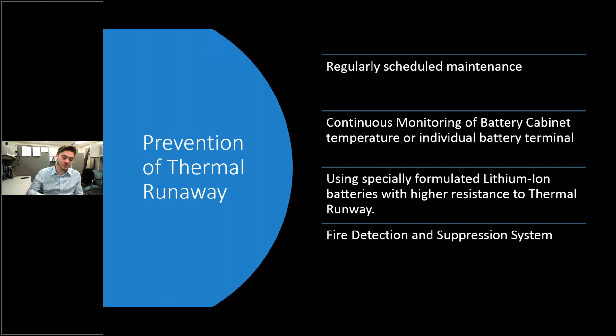So now let's discuss some fire hazards. Now, the benefit of increased energy density is paired with the increase of fire risk. By understanding the risk of fire, improvement toward fire detection and suppression can be made. Examples of detection methods include smoke detectors and/or aspirating smoke detectors. Examples of fire suppression include inert gases, water spray, foam, and water mist systems, which we'll cover in later slides.